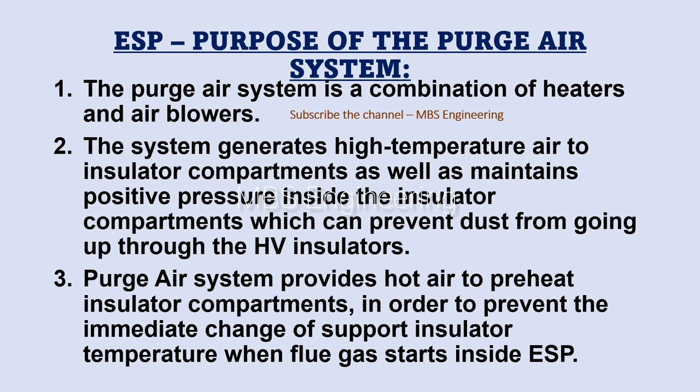Point three: the purge air system provides hot air to preheat insulator compartments in order to prevent the immediate change of support insulator temperature when flue gas starts inside the ESP.